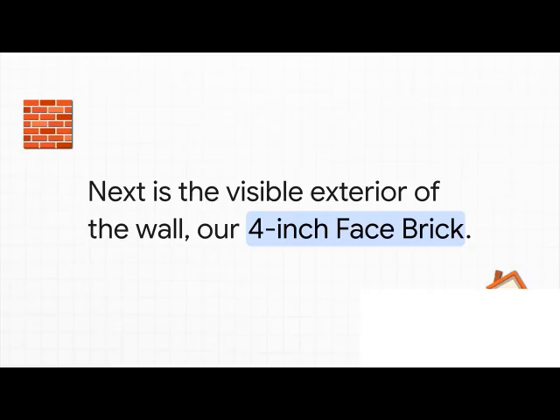Let's write that down. Okay, next up is the brick on the outside of our building. This is a pretty standard 4-inch face brick. Looking at our charts again, we find that the R value for this layer of brick is 0.44. So as you can see, it gives us a little more resistance to heat flow than that air film, but it's still not a huge number by itself.